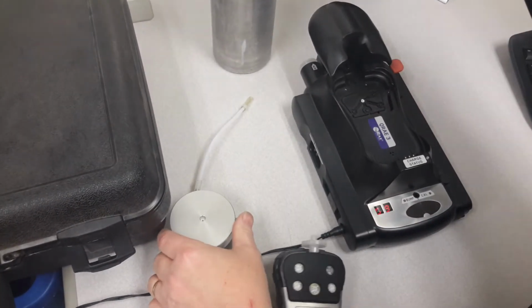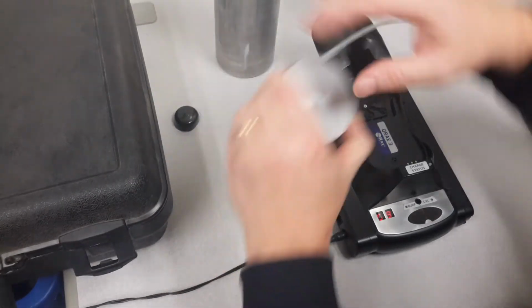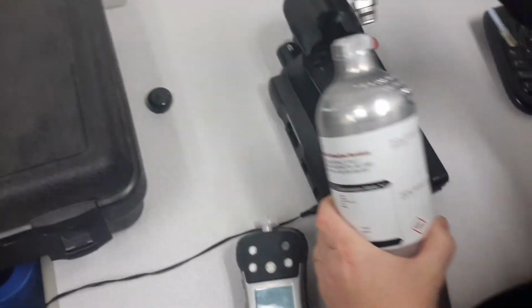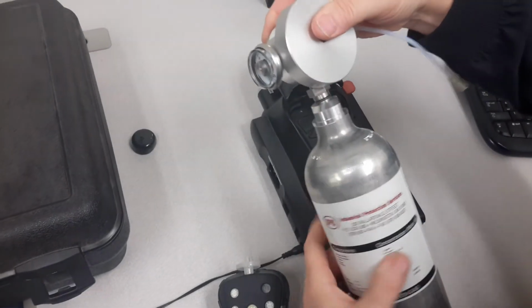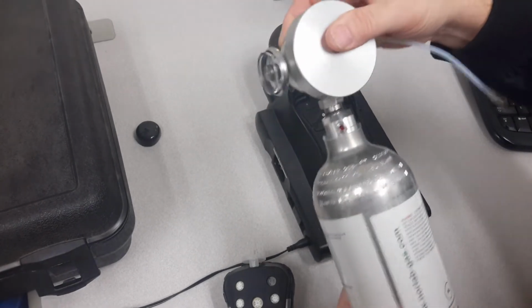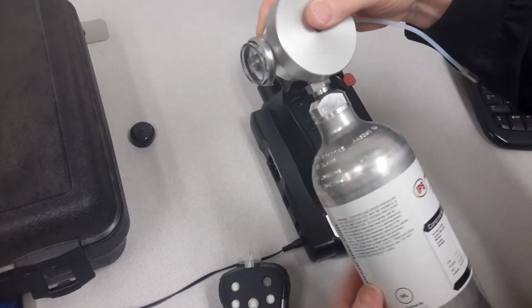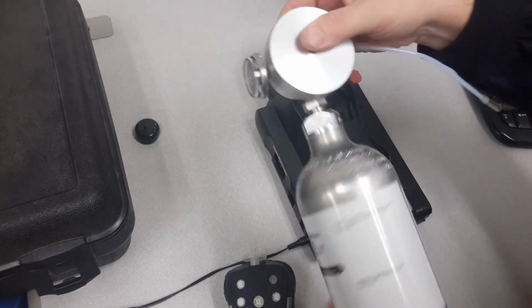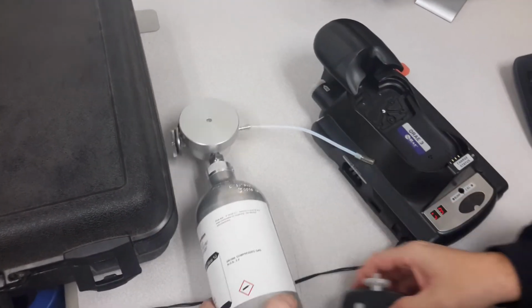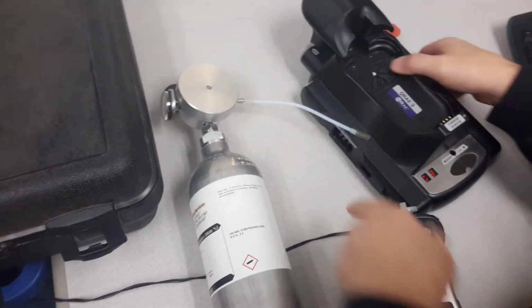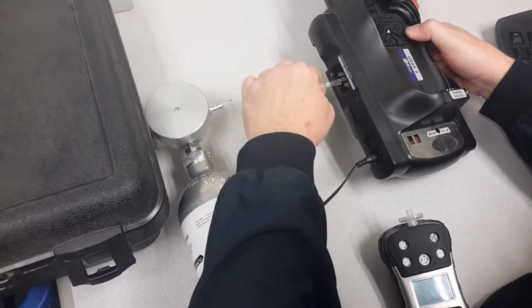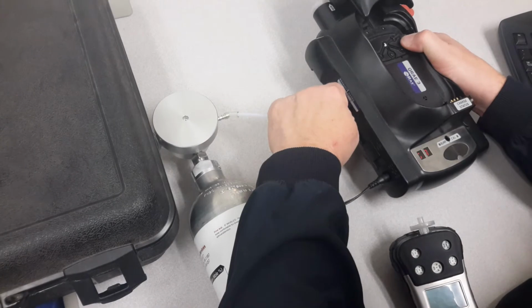You have your calibration gas. Go ahead and take the top off here. Set the regulator in the gas bottle, but you don't really need to tighten it all down yet until you're ready to calibrate, because you'll just be wasting gas. So just set it in there for now, and then go ahead and plug it into port 1 on the Cradle.